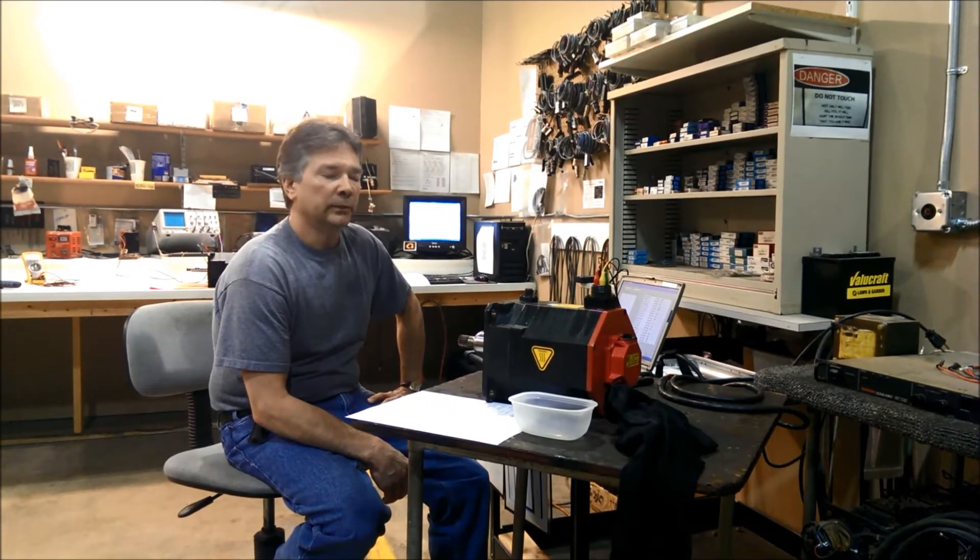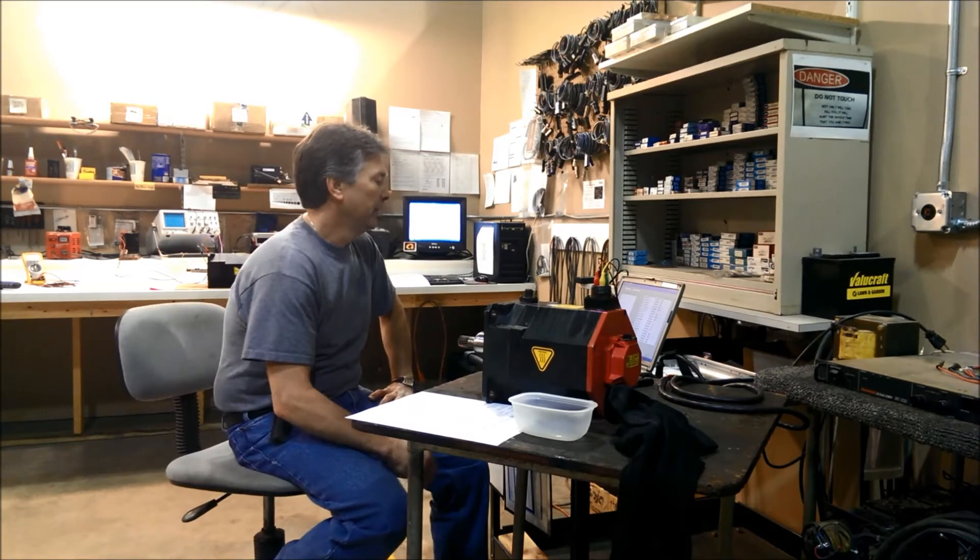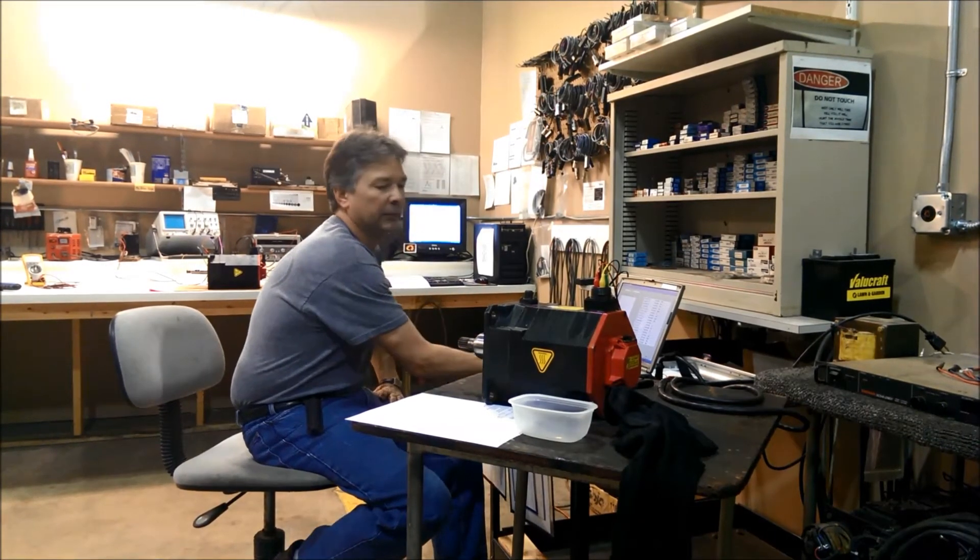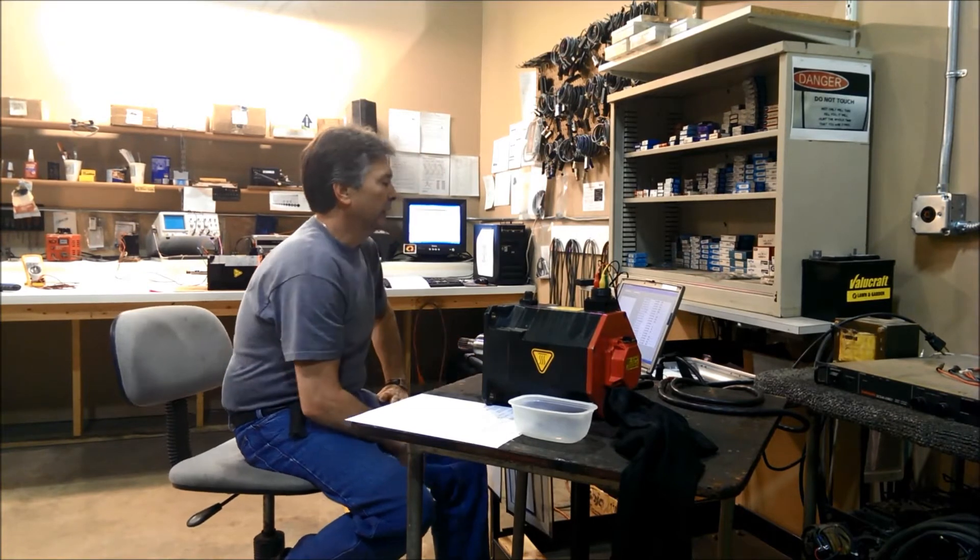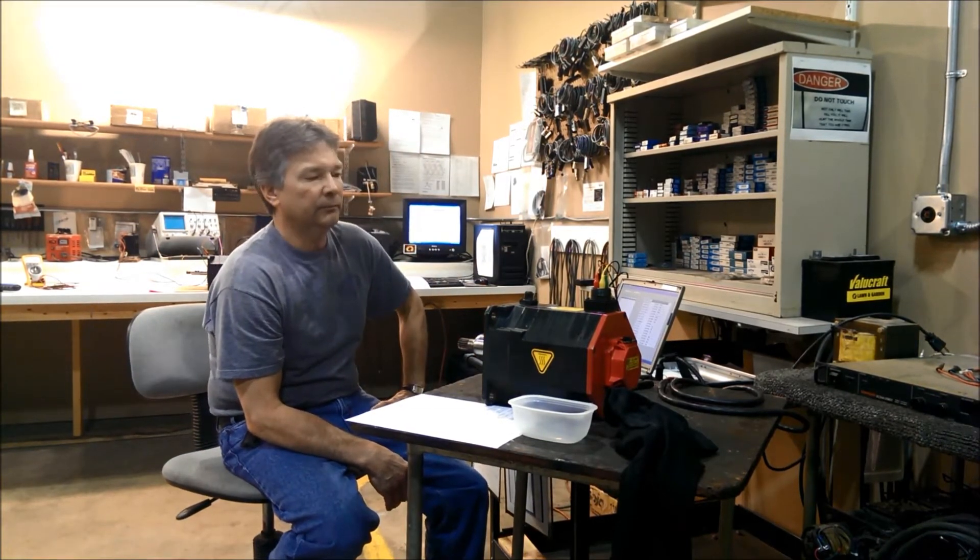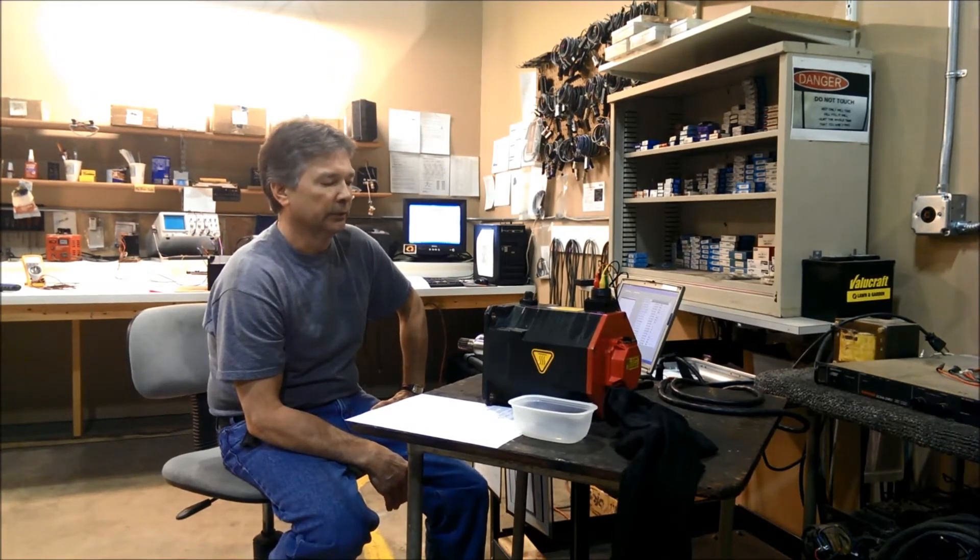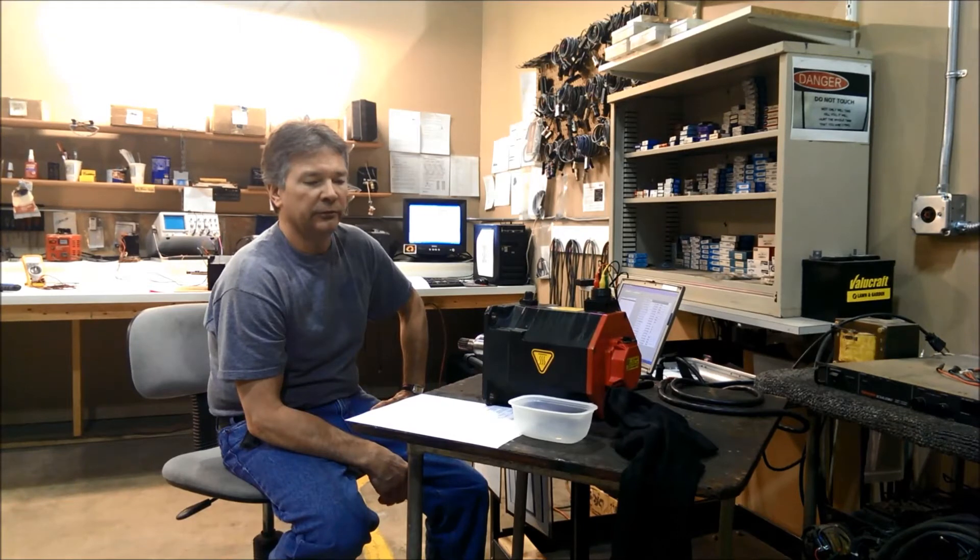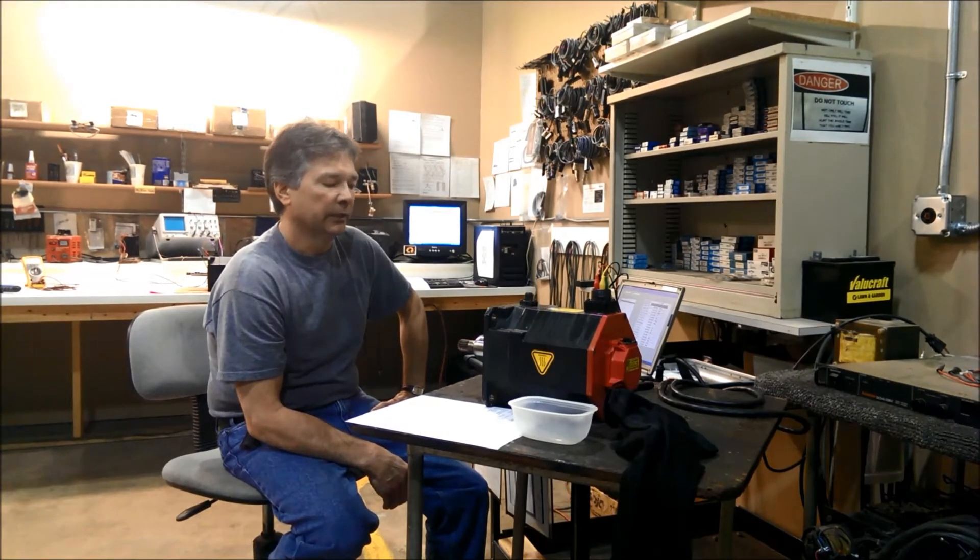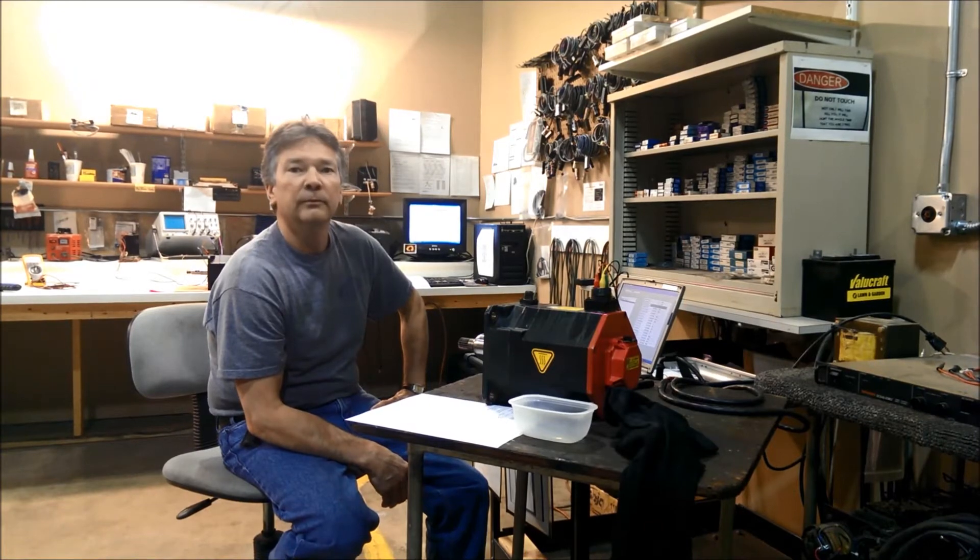So what we'll do is hook it up to this equipment here, then we'll enter the parameters for the motor and run a test on it. It'll run through the various tests, surge the windings, and verify that the insulation is intact and that the motor windings are up to specifications.